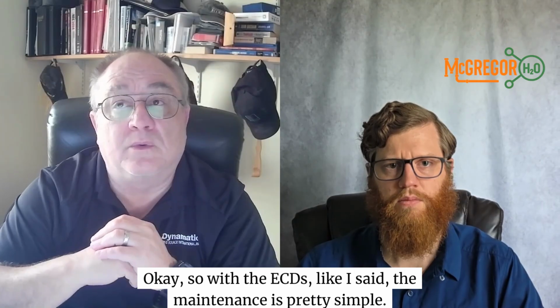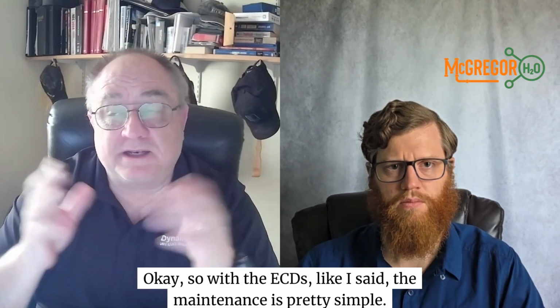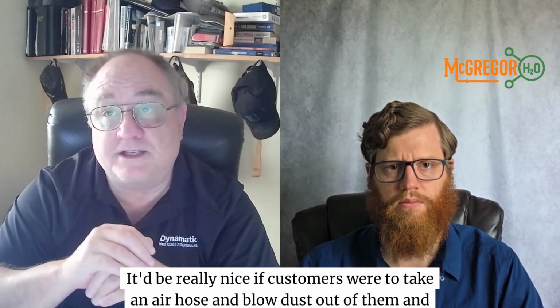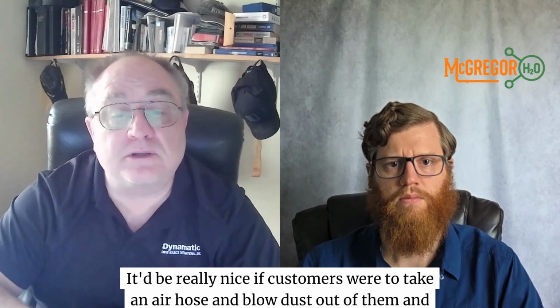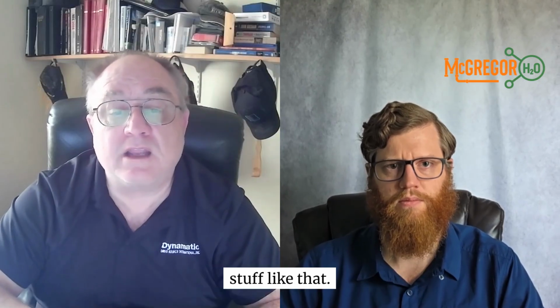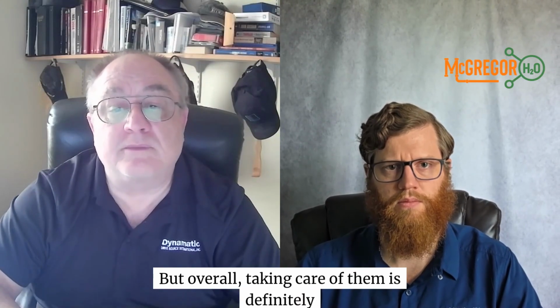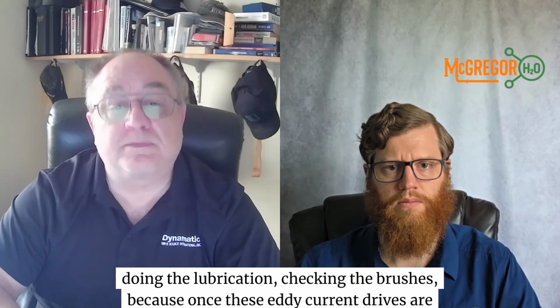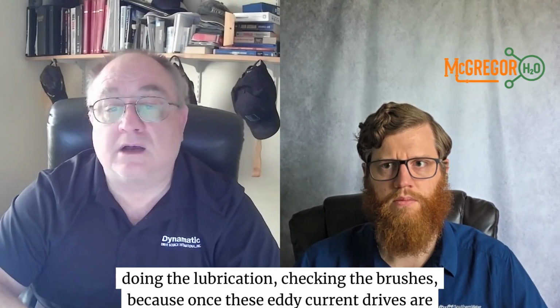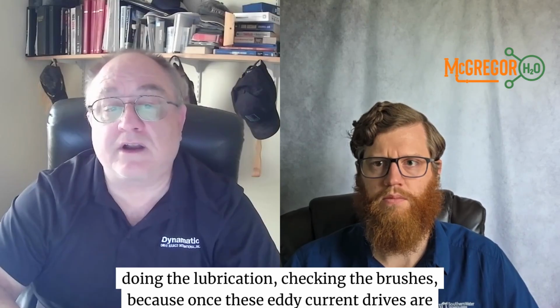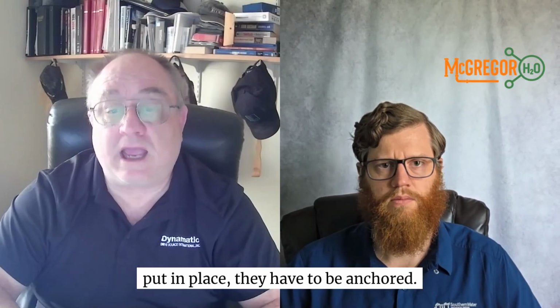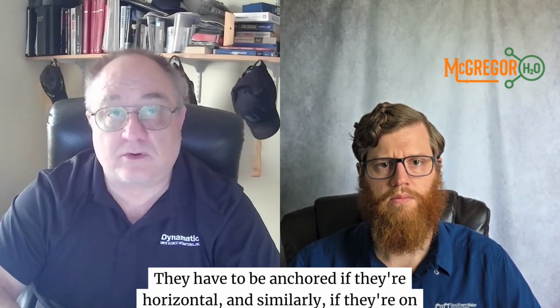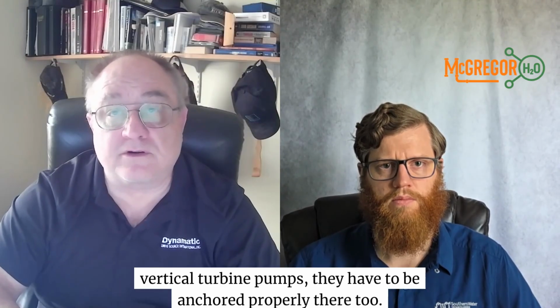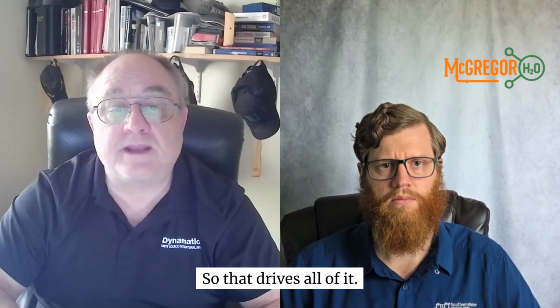Okay, so with the ECDs, like I said, the maintenance is pretty simple. It'd be really nice if customers were to take an air hose and blow dust out of them and stuff like that. But overall, taking care of them is definitely doing the lubrication, checking the brushes, because once these eddy current drives are put in place, they have to be anchored. They have to be anchored if they're horizontal, and similarly, if they're on vertical turbine pumps, they have to be anchored properly there too. So that drives all of it.